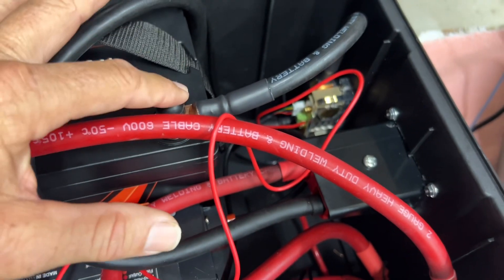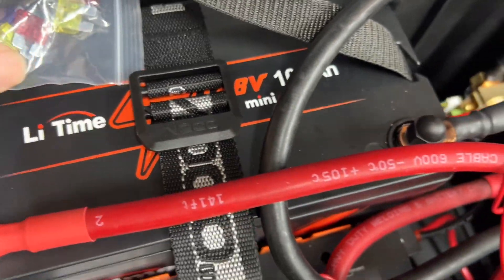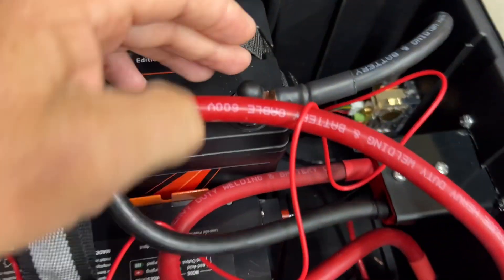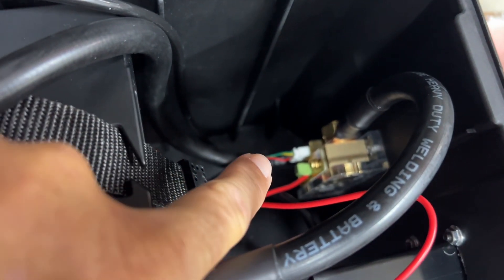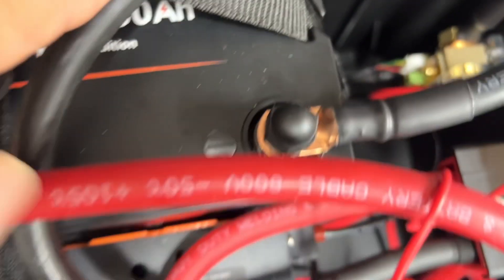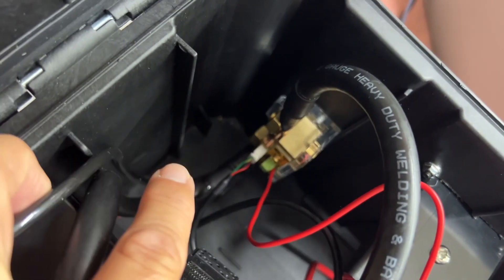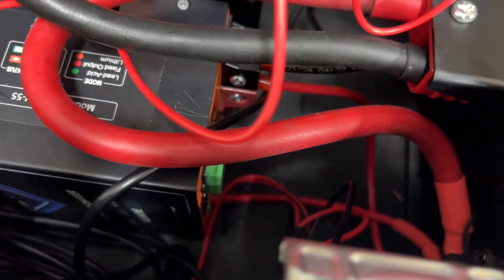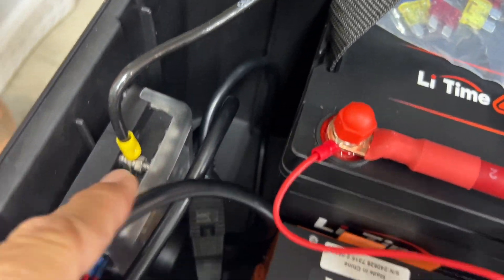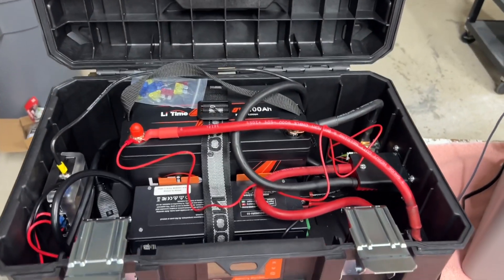Let's look at the negative circuit. We have the negative post on the LiTime 100-amp-hour mini — nice compact battery that fits really nicely in this box. We're coming out of the negative side going into the shunt. It is direct current. Then you have this main coming out of the other side going right into the Anderson connector. We're also using that bottom connection as a little bus bar. One wire goes to the negative on the converter charger, and the other negative comes around over the top into our six-way fuse block. So that's all the components inside — let's take a look at this thing in full operation mode.